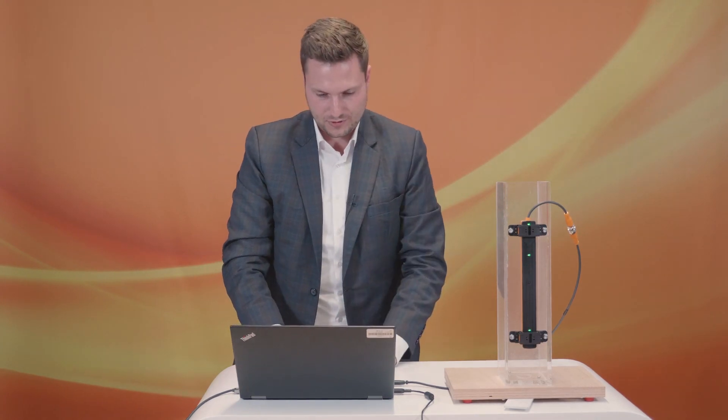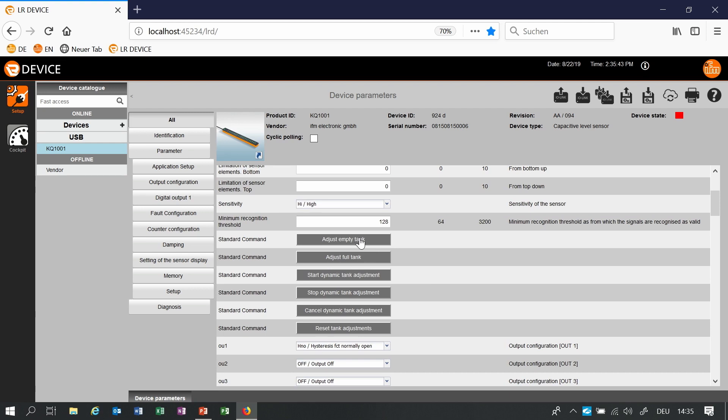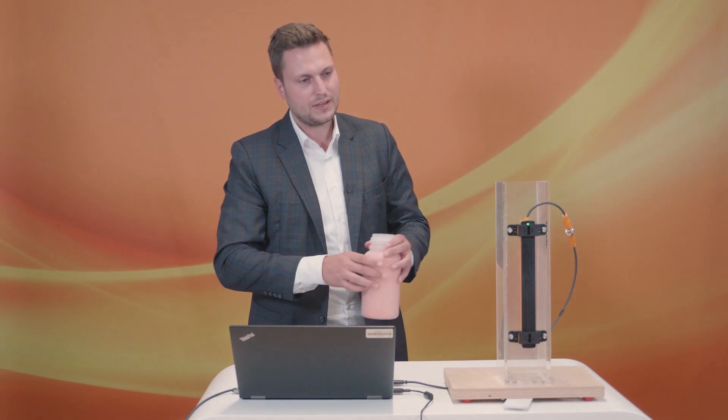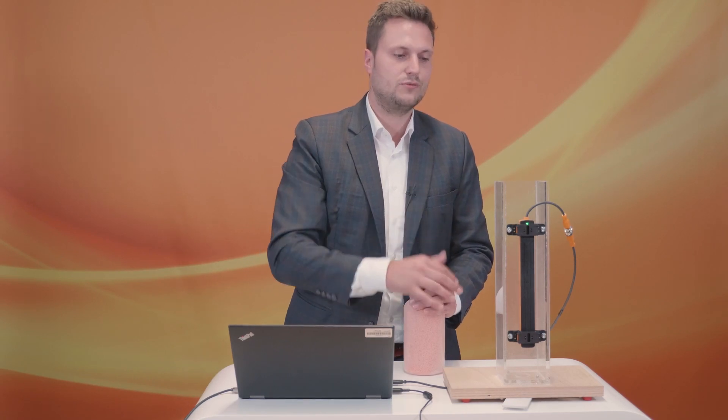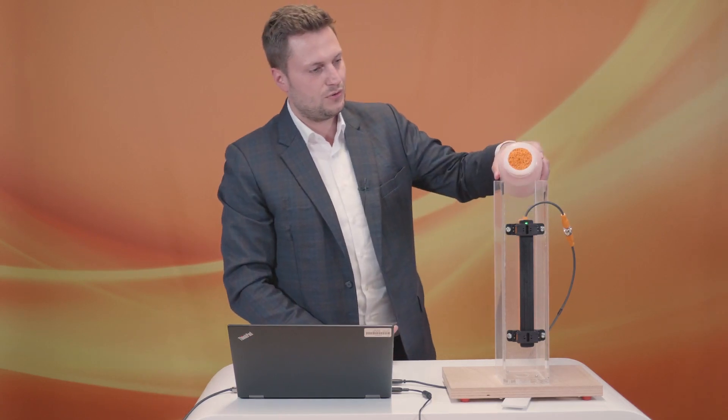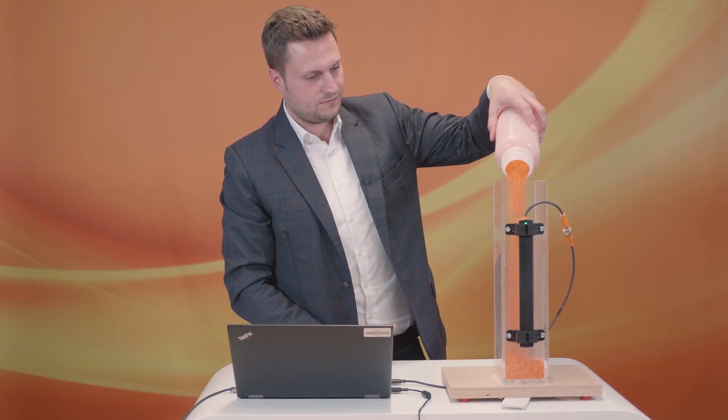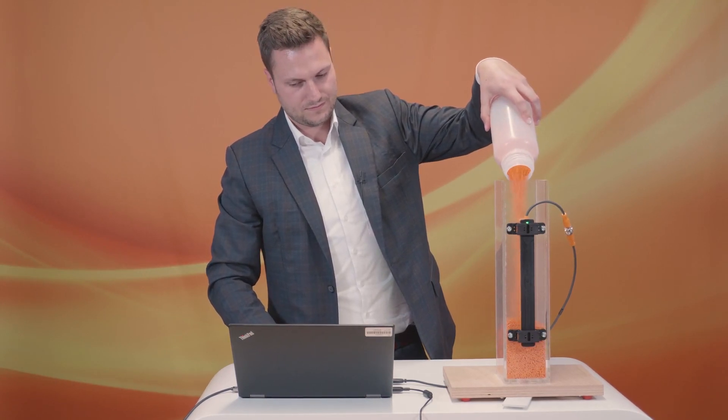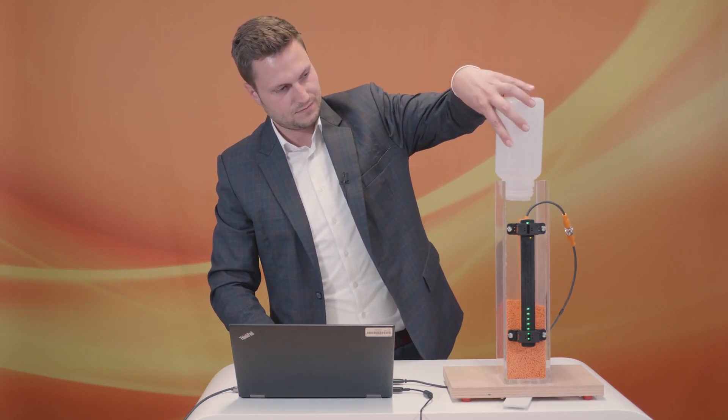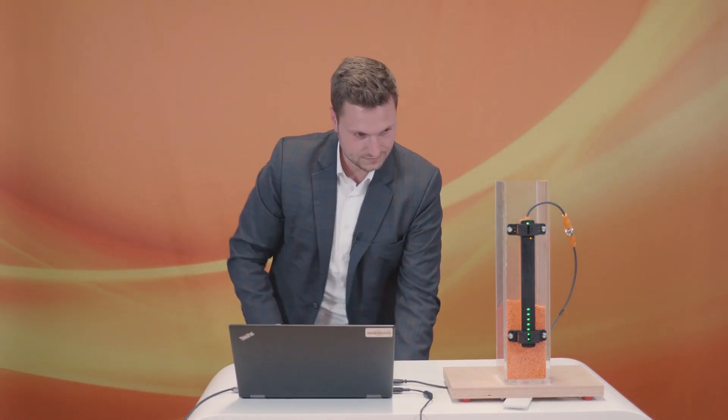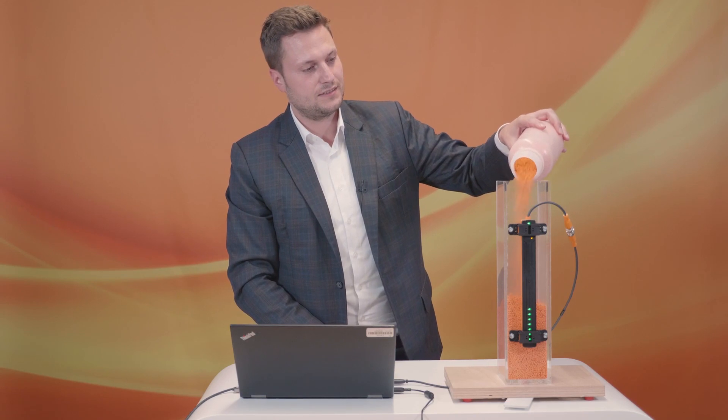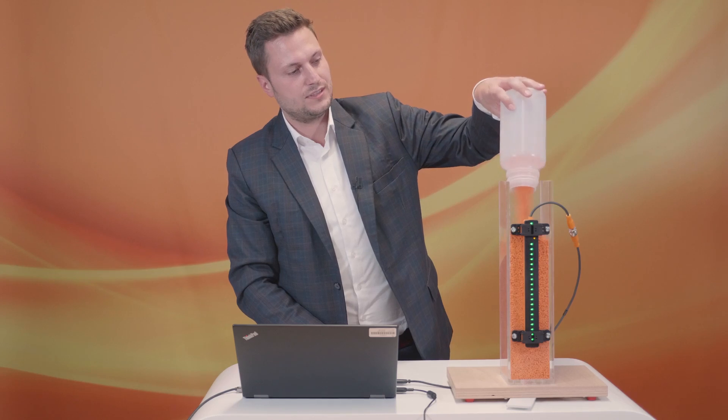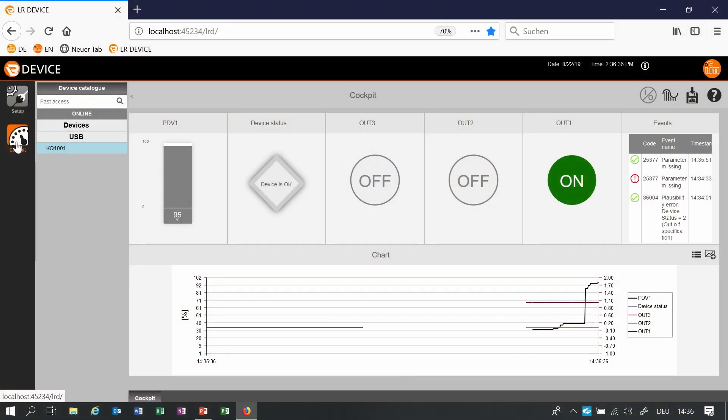Then we will mount it on the surface and like I did it before we just have to make one empty teach. The direction of the sensor is now top and we made the empty teach so the sensor is able to detect everything which is in front of it. In this case we use plastic granules. This is actually a very hard detectable granule because the dielectric constant is very low but we are able to detect it even without a full teach.